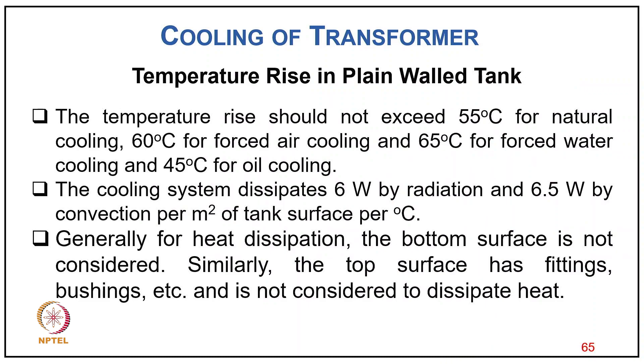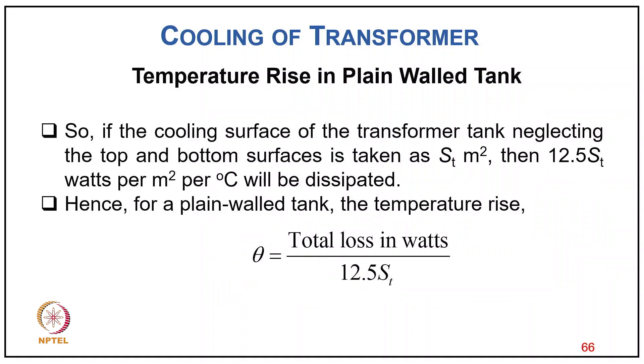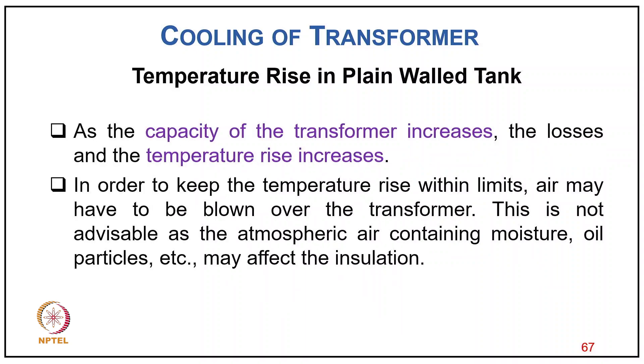For temperature rise in a plane wall tank: temperature rise should not exceed 55°C for natural cooling, 60°C for forced air cooling, 65°C for water cooling, and 45°C for oil cooling. The cooling system dissipates approximately 6 W by radiation and 6.5 W by convection per meter² of tank surface per degree Celsius. The bottom and top surfaces are not considered for heat dissipation. Total dissipation is 12.5 W/m²/°C, and temperature rise θ = total loss (W) / (12.5 × ST), where ST is the surface area of the four tank walls.